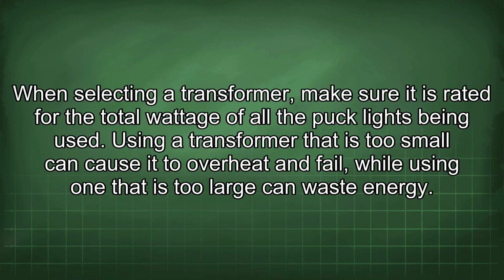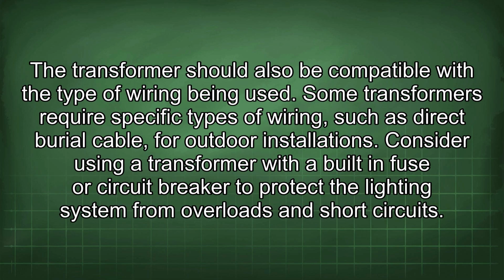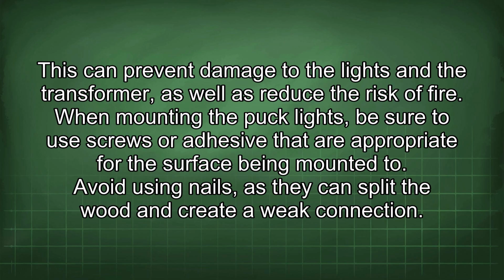When selecting a transformer, make sure it is rated for the total wattage of all the puck lights being used. Using a transformer that is too small can cause it to overheat and fail, while using one that is too large can waste energy. The transformer should also be compatible with the type of wiring being used. Some transformers require specific types of wiring, such as direct burial cable for outdoor installations. Consider using a transformer with a built-in fuse or circuit breaker to protect the lighting system from overloads and short circuits. This can prevent damage to the lights and the transformer, as well as reduce the risk of fire.